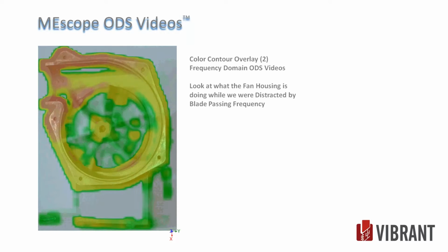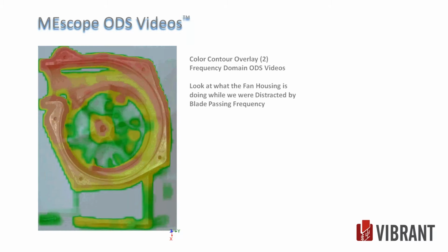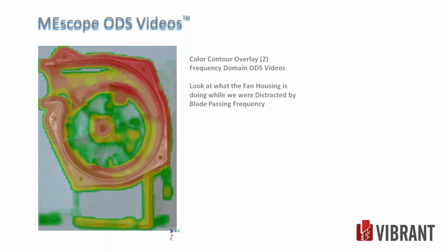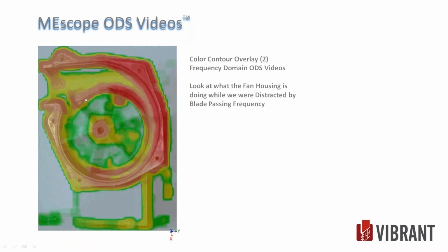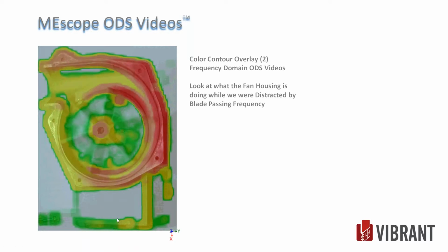And I put a different color contour on that was a little more scaled to the motion, and gives you a nice response there. So interesting. The 1 times RPM, it's doing something, and then the blade passing is pulsating as well.